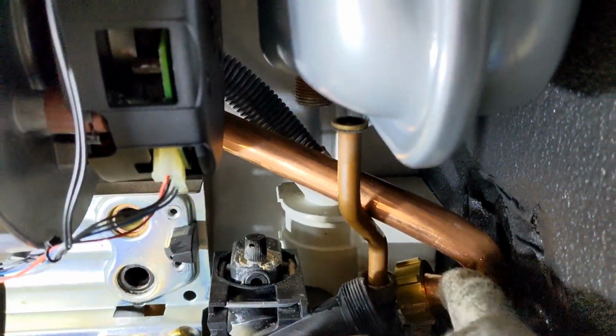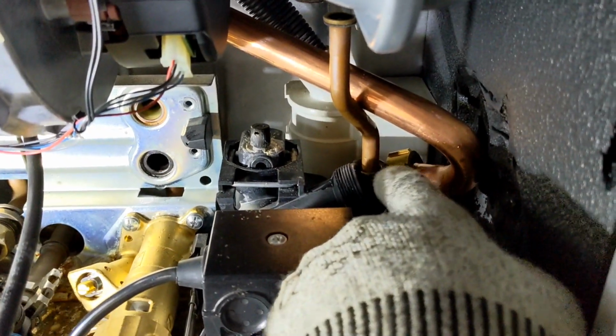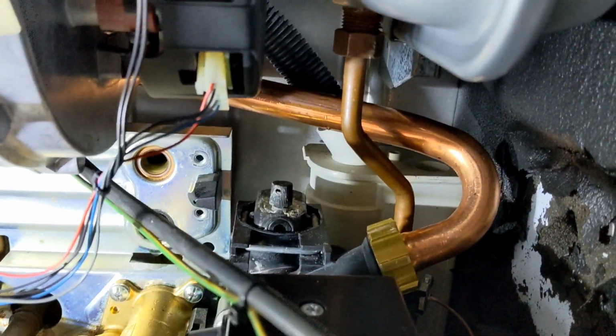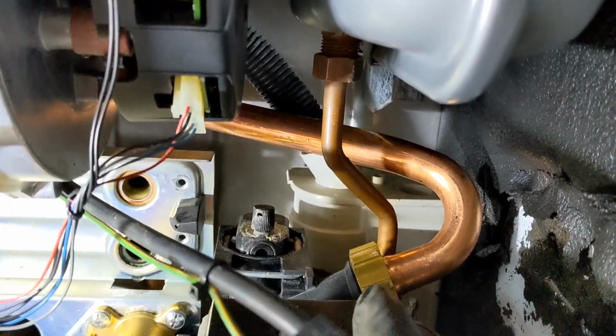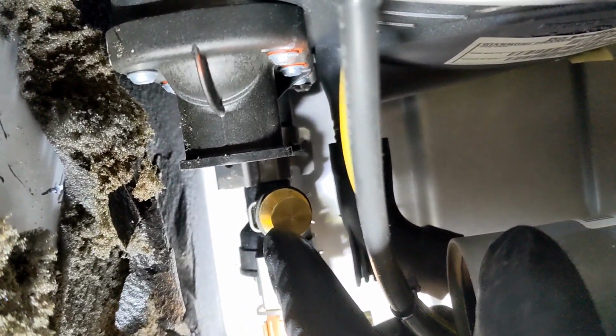Now I've got it into position, I can put the O-ring on there, put it into the pump there, put that side into the main heat exchanger, and then we can deal with the flow side. Alright, return side's all done, expansion vessel connection's done, pump connection's done, that's all in, that's clipped in there. These come with a blank up there because on the new Vaillants the pressure sensor would go there, and that there will be blanked off.